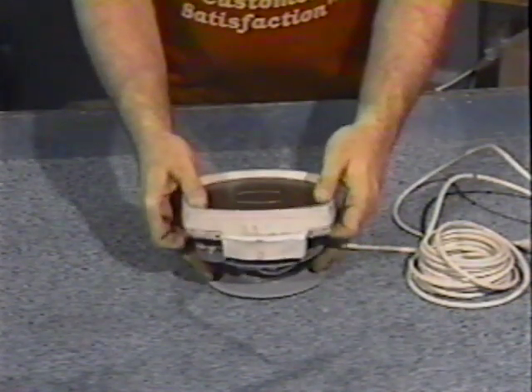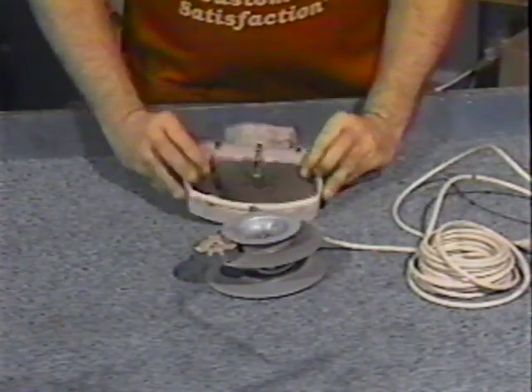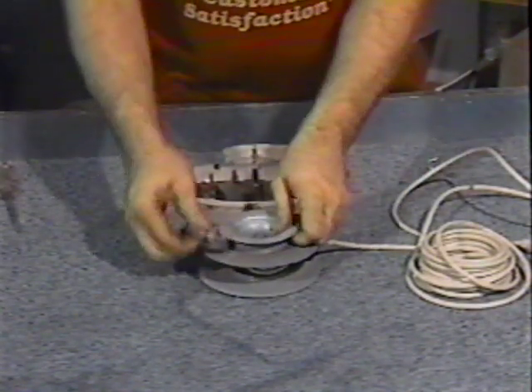To inspect the power cord, remove the reel from the cover. Now remove the reel cap retaining screws and cap to allow for a thorough inspection of the cord. Inspect the cord in the strain relief area and the cord exit point. After inspection, reassemble the reel to the housing and wrap the cord.